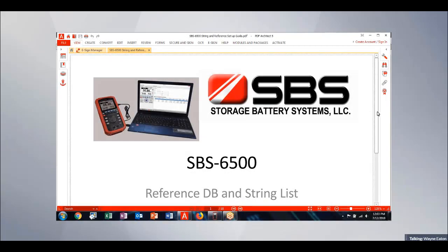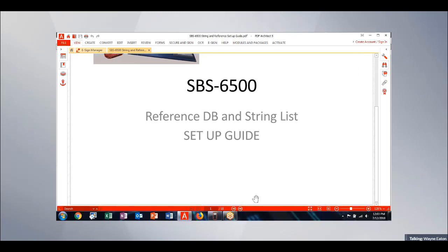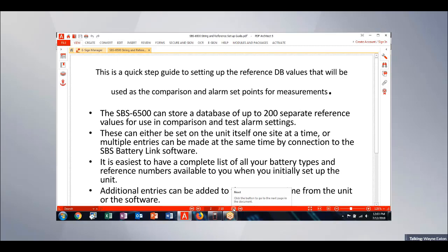So with the SBS-6500 unit, the unit was developed to handle a lot of the functions that the other internal resistance testers on the market can't do. We accomplish this by our configuration of our memory and our file storage, so that we can literally track the lives of our batteries across their entire life without ever having to go back in and reprogram or delete information off the unit. The unit will actually record up to 20 years worth of maintenance data without having to modify anything on the unit once we get it set up to start taking the readings.